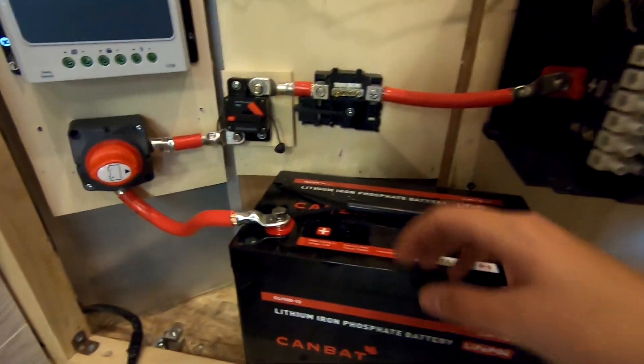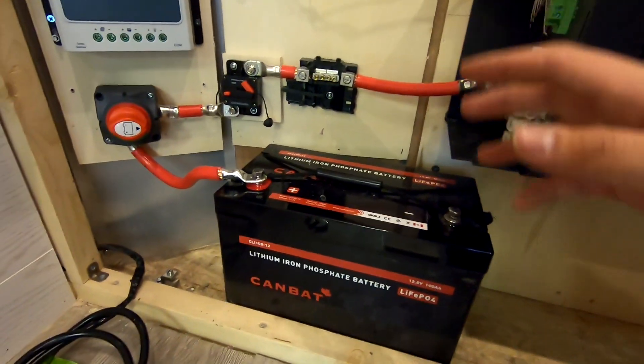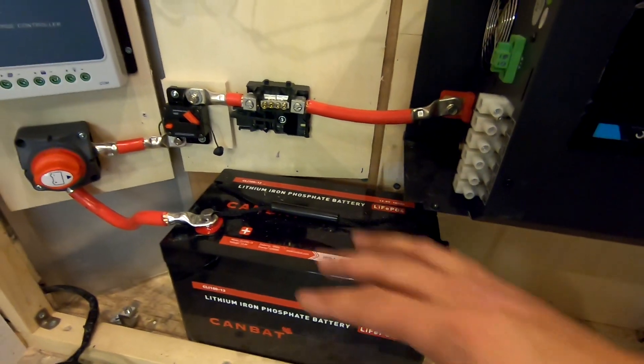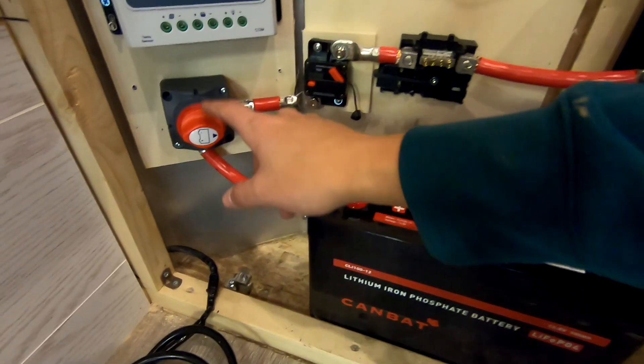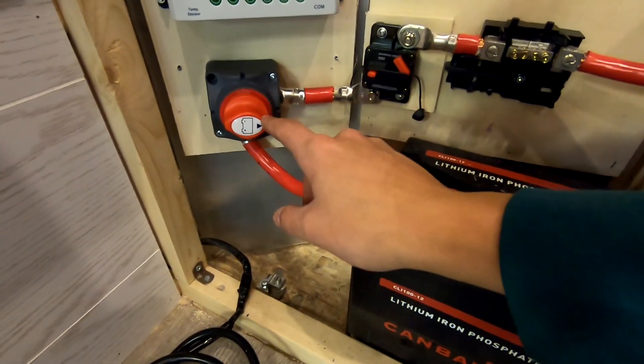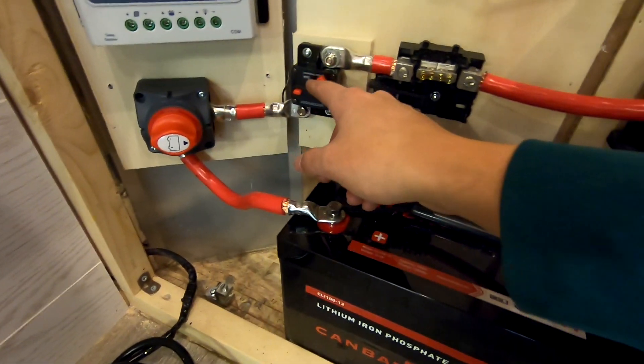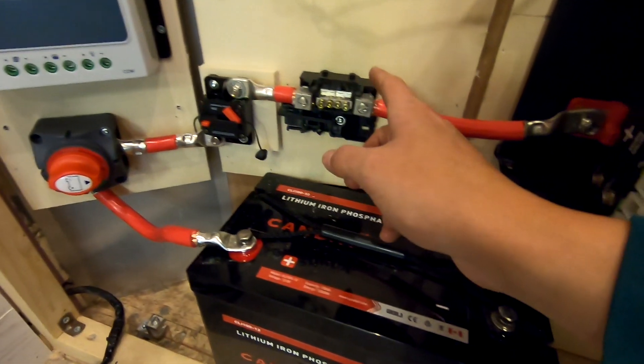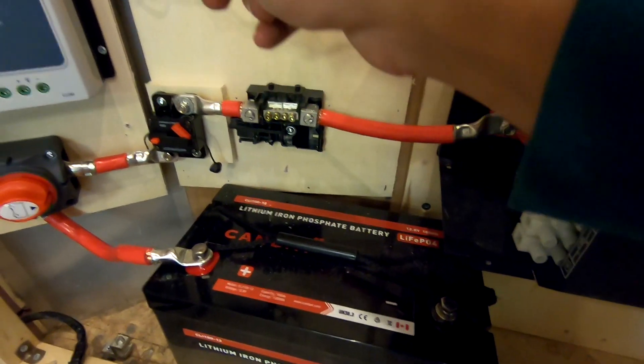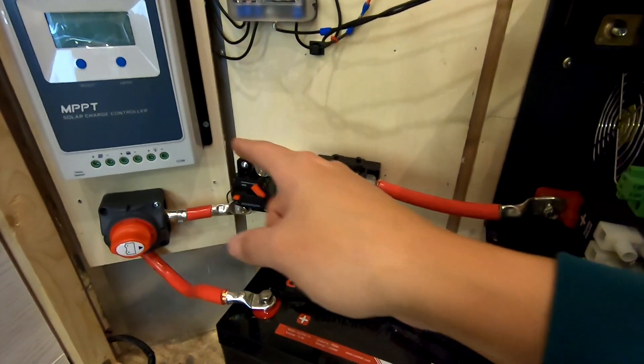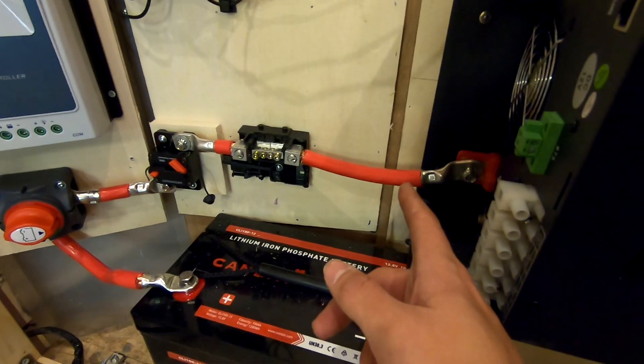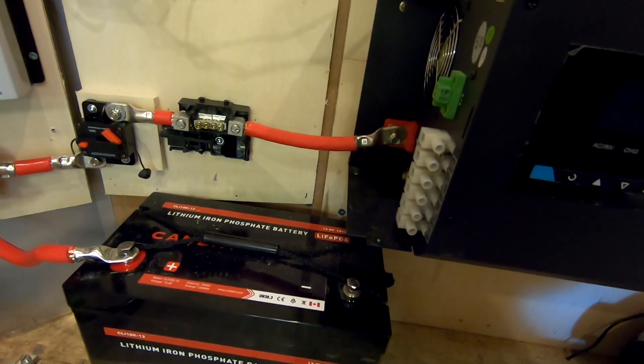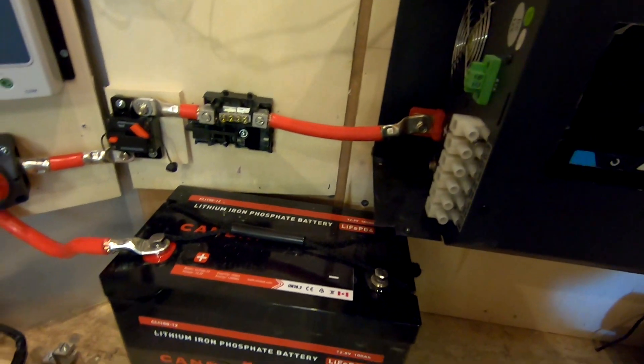I just finished the first phase of wiring here. This is the 2-gauge cable to the inverter. This mess here is my cable going from battery to cutoff switch, which is off right now, and then to my 200-amp breaker switch. From my breaker switch, I'm going to the positive bus bar, which will be feeding the fuse block, the charge controller, and also going to the inverter. Now just time to run the wires for the negative, and pretty much near there, almost done.